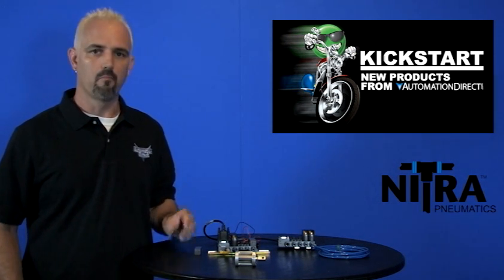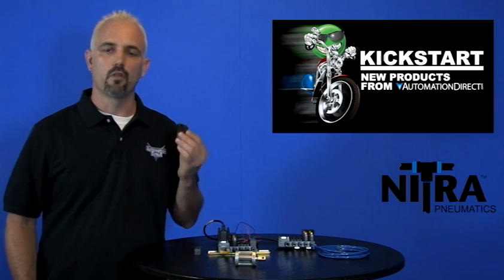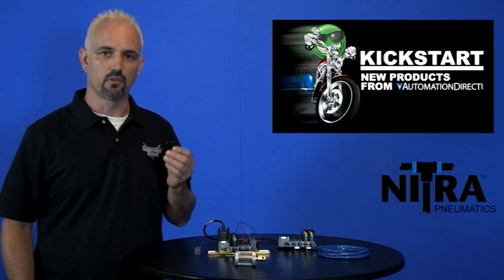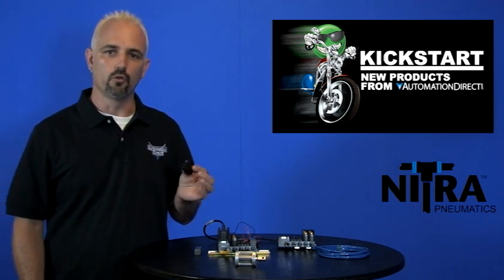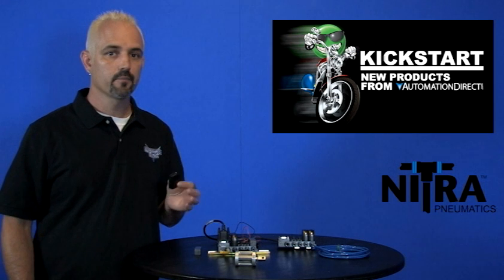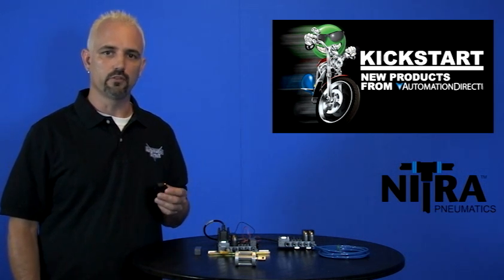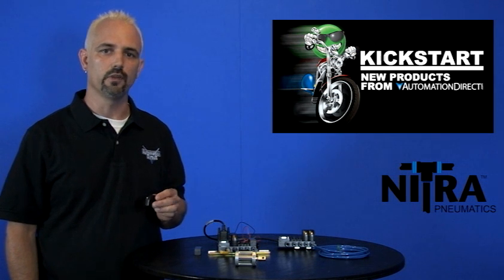What we have here are called modular control valves. These are a 3-way, 3-port poppet valve, 2-position, single solenoid with a normally open or normally closed spring return. These come in a 12V DC, 24V DC, or 120V AC coils.